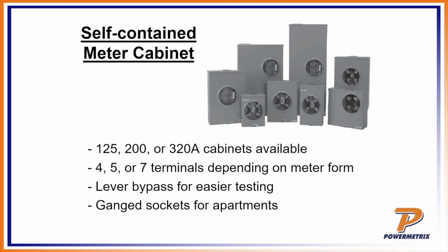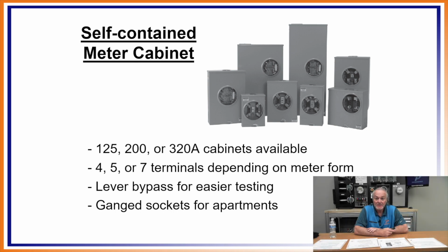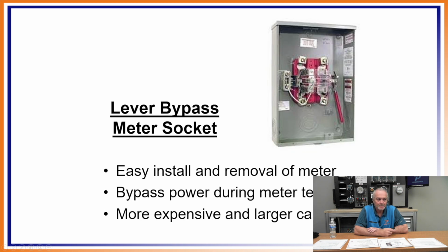Self-contained meter cabinets. Typical currents on these are going to be 125, 200, or 320 amps. You've got 4, 5, or 7 terminals depending on the meter form. Those will take care of all your self-contains. Then you've got lever bypass for easier testing and also safety. And then you've got, once again, the gang sockets for the apartments.